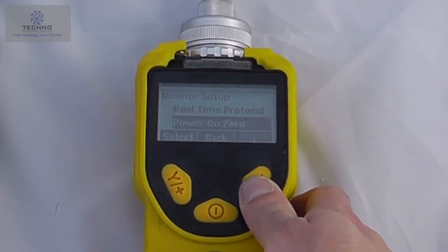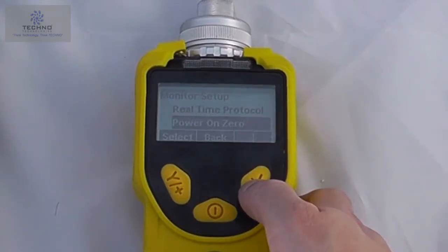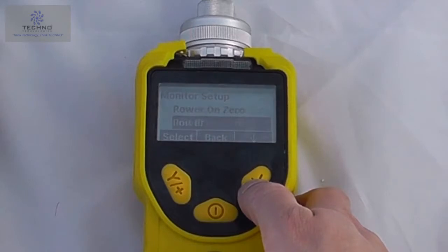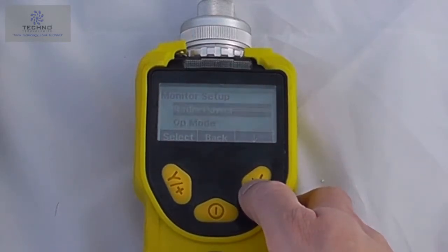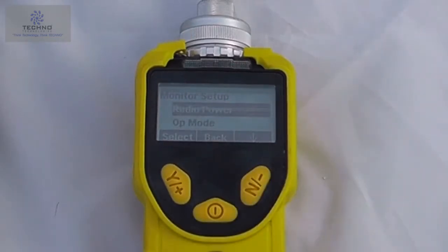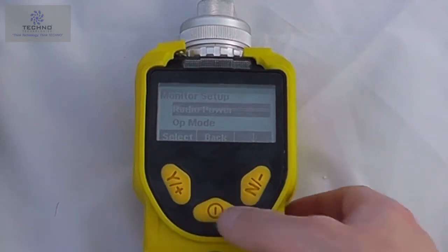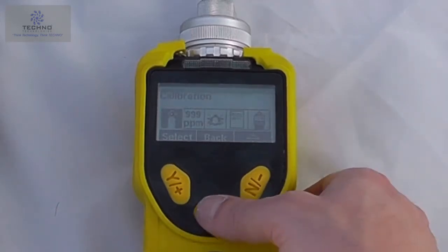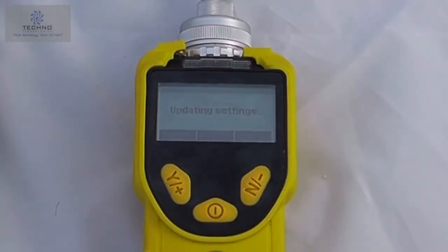real-time protocols, power on zero, so whether it does a zero at startup, unit ID, LCD contrast, lamp ID, if we particularly want to put one in, PAN ID, and the PAN ID is mainly for use with things like the MeshGuard system when we want to look at wireless options. So if we go back into the general instrument operation, we've got a good idea of the menus now.